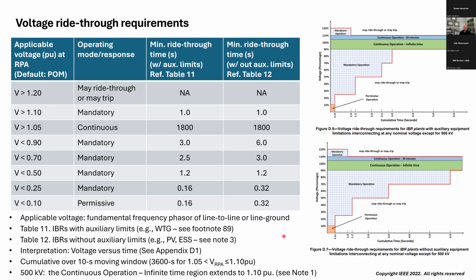These time durations are cumulative over a 10-second moving window, except for this area above 1.05. That's going to be over a 3,600-second window. Another key note is for 500 kV connections, this continuous range from 1.05 to 1.1 is going to be infinite time. This whole row really goes back to the ANSI standards of how equipment is rated, and that's why it's different for 500 kV than say 230, 161, etc.